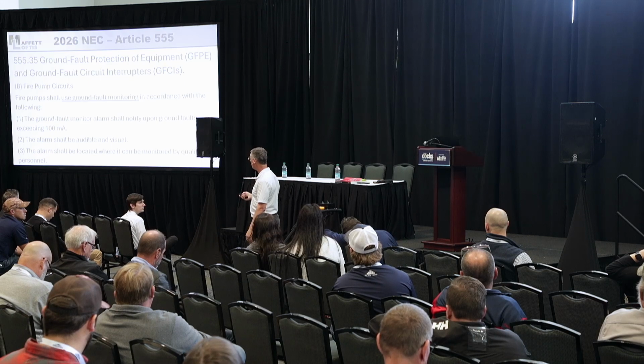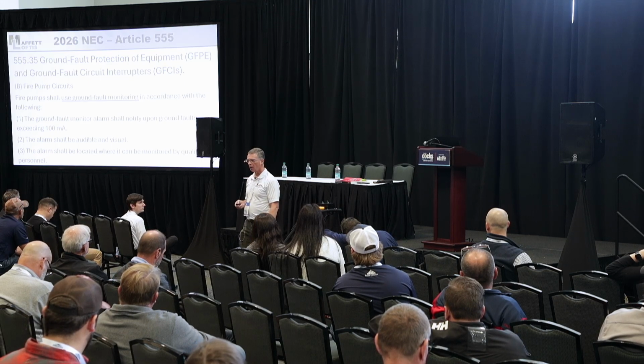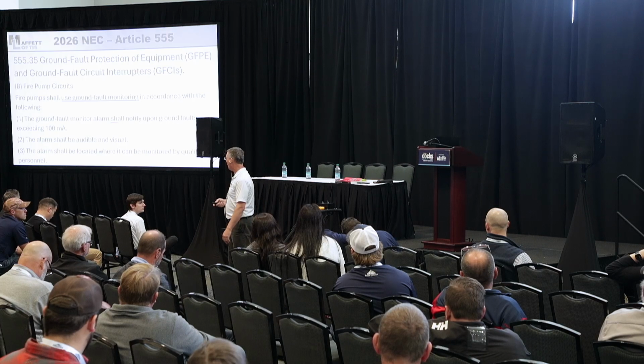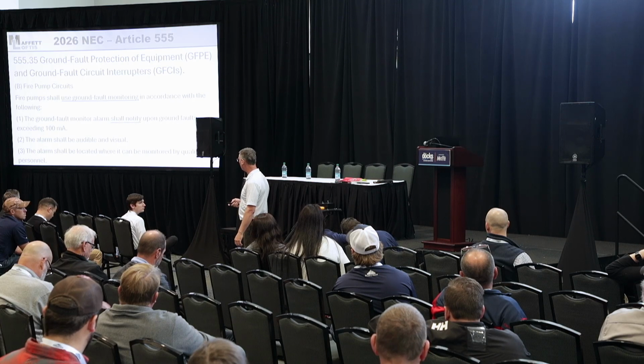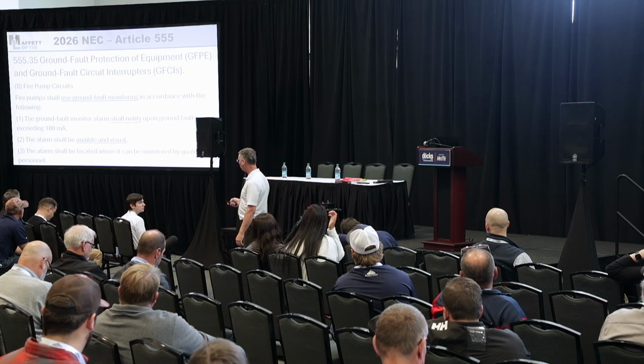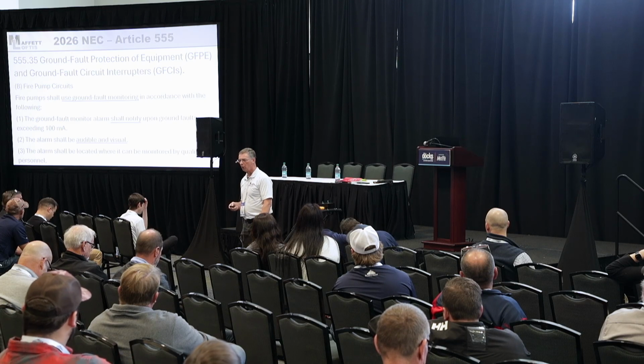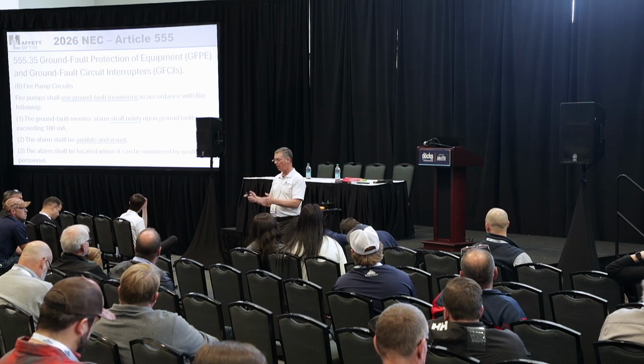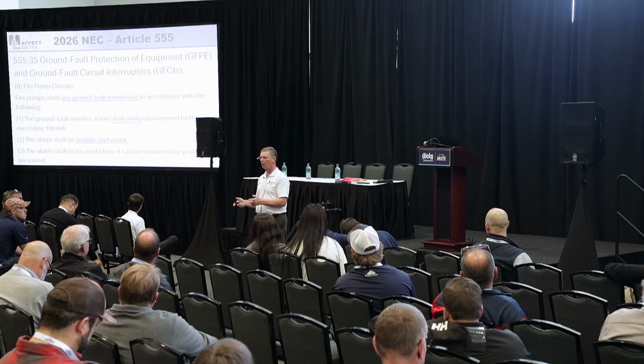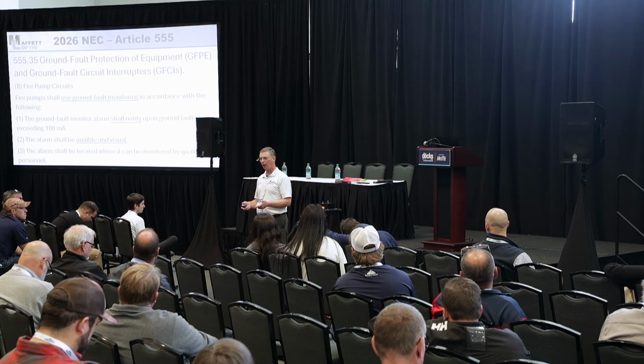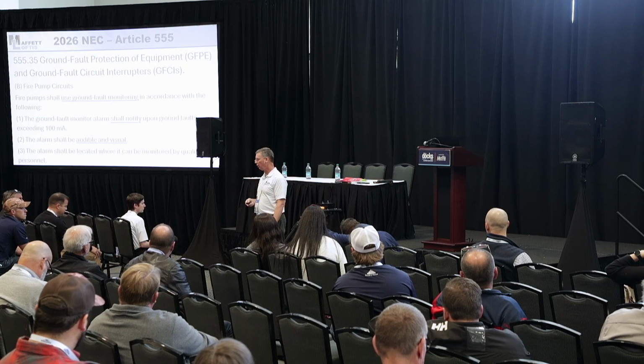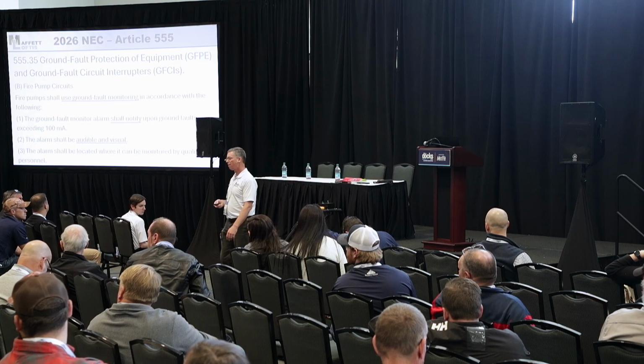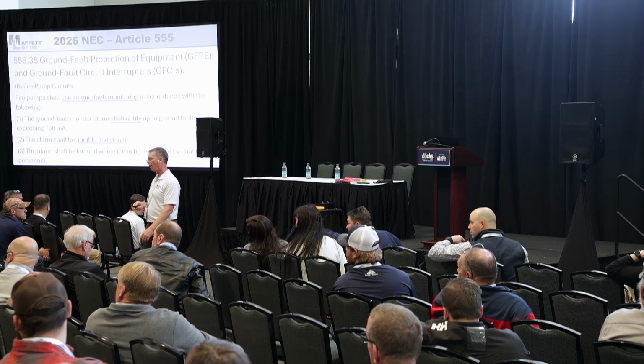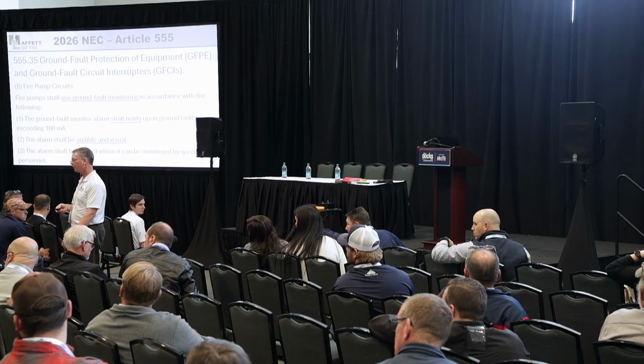So what we're saying is, for fire pumps, we can use a ground fault monitoring system to monitor for leakage currents, and if it reaches above that 100 milliamp, then it will notify with audible and visible alarms. You can go out there, shut it down temporarily, fix the issue that's causing the leakage current, then power it back up, and you've got a fire pump without leakage current again. A fire pump runs when there's a fire, and the code states that it is not allowed to shut off.